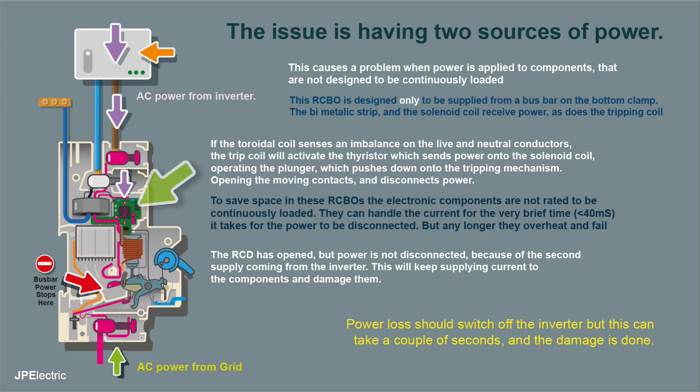These electronic components are designed to be energised for a very short time — usually the opening of the RCD, which is milliseconds. Any longer and they're going to overheat and fail. Because we've got a second source of power from the top of the RCBO, these components will remain energised until that generating source stops producing power, and that might be too long for these components and they burn out.